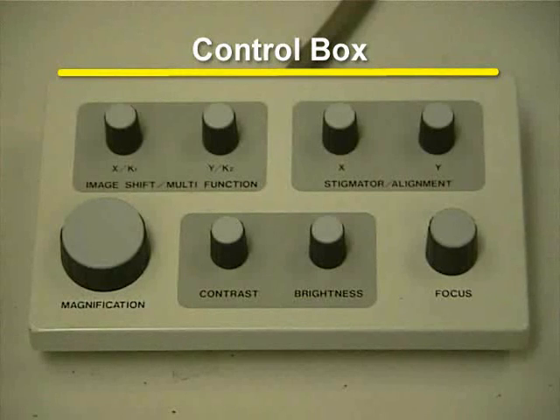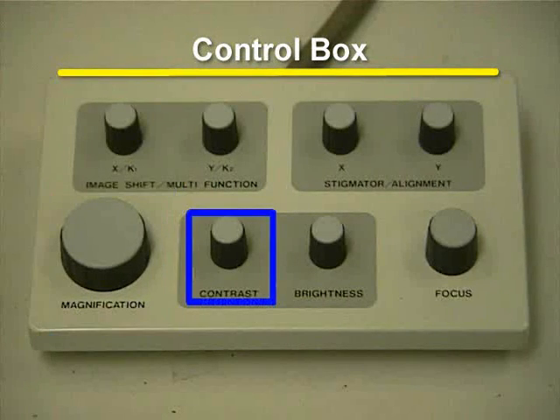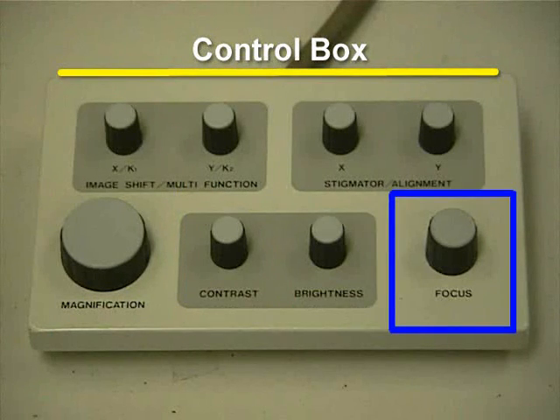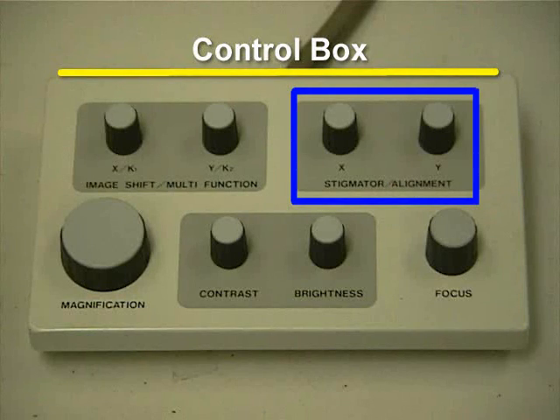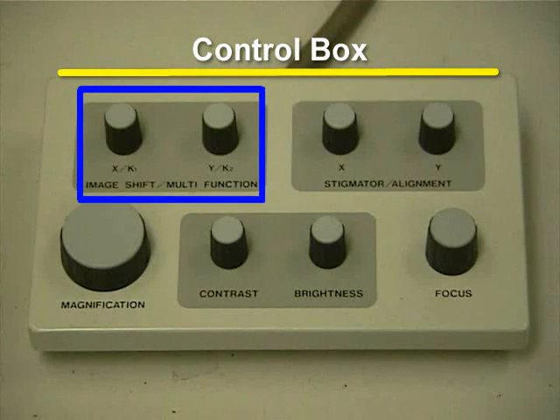The control box has various knobs to change the magnification, contrast, brightness, and focus. The knobs on the top right are used to adjust the stigmation and the X and Y directions when the stigmation screen is open. The two knobs on the top left, which are called the Image Shift Multifunction XK1, YK2 knobs, have different uses. Their use is defined in the K1, K2 display area of the status bar in the SEM software.